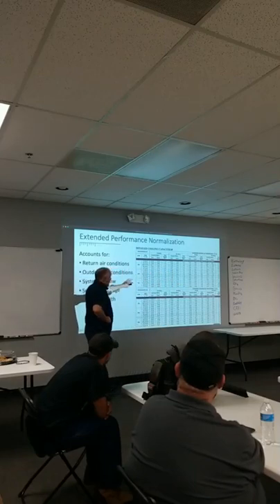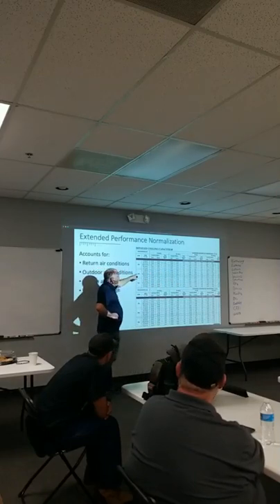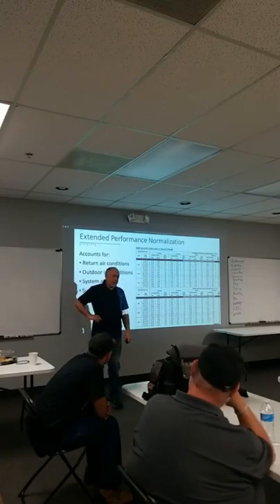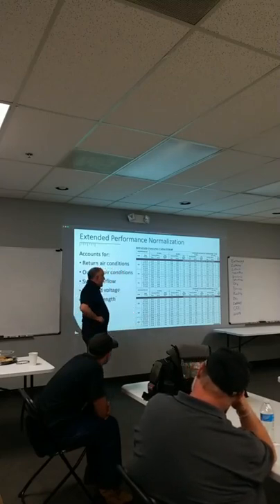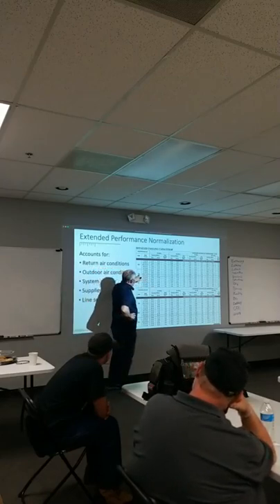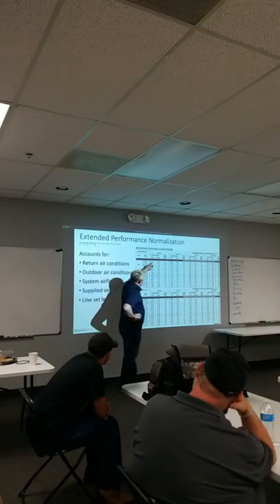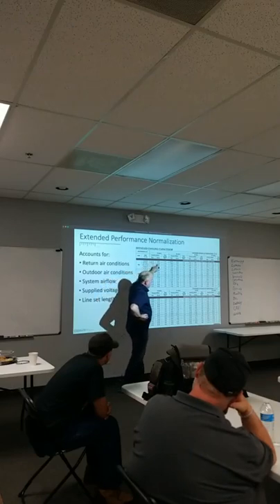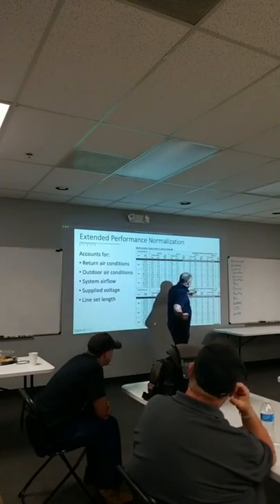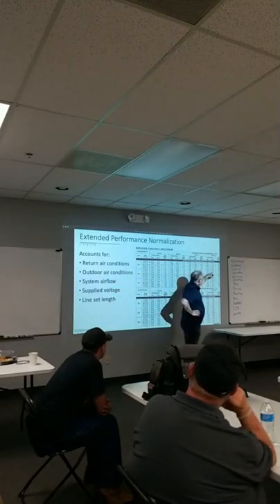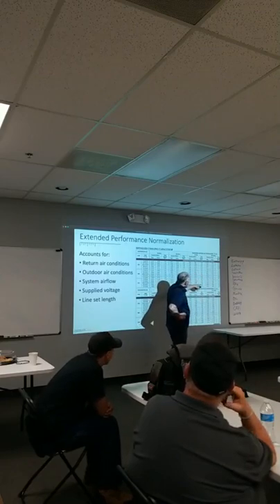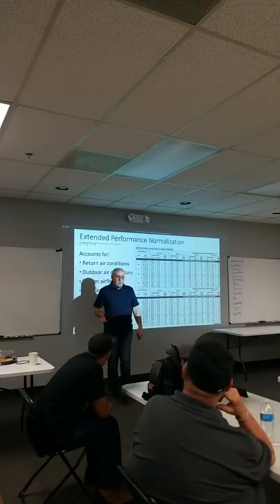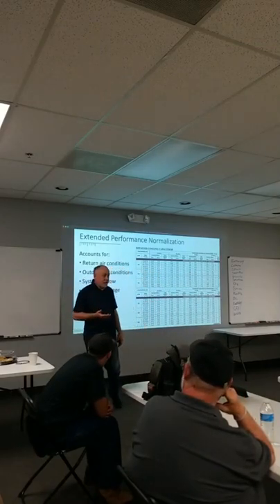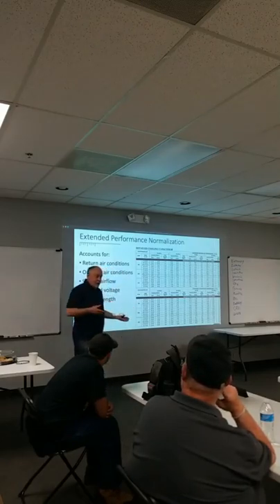Now, that is AHRI conditions. It's 400 CFM per ton, 95 degrees outside, 67-degree wet bulb, and that's equivalent to 80 degrees at 50% relative humidity. Outside of that, this system could be doing up to 21,000 BTUs of cooling, right? And over at this other end, it could be doing as low as about 9,000 BTU sensible. It's a good total here, about 15,000, I think, on the low end of that. So your 18,000 BTU system really doesn't do 18,000 BTUs of cooling unless it's under AHRI conditions.